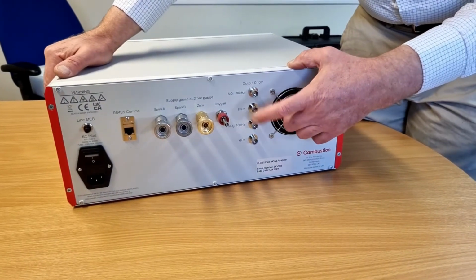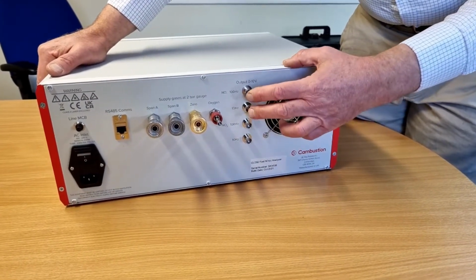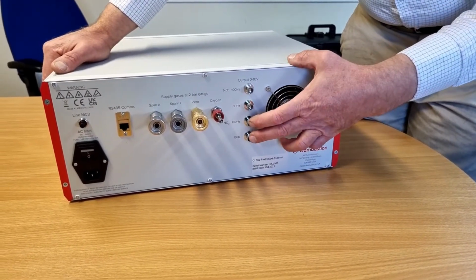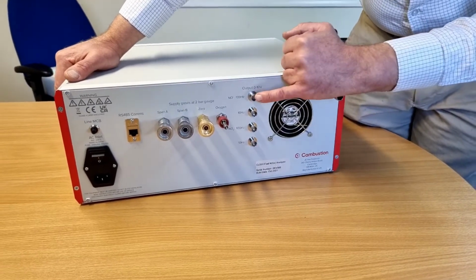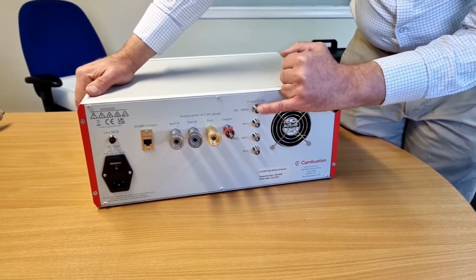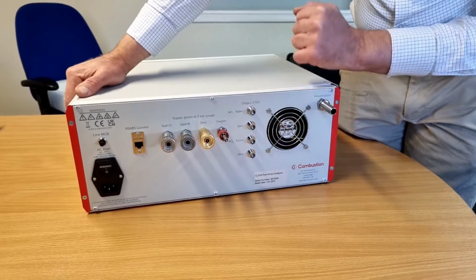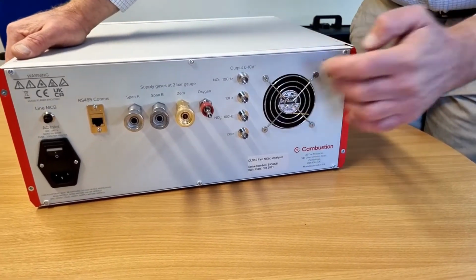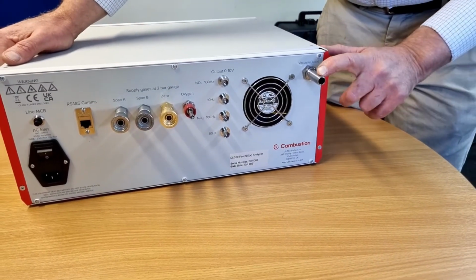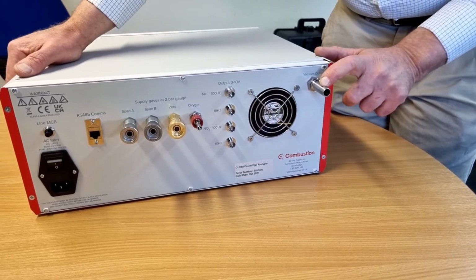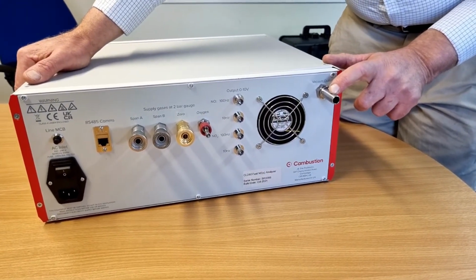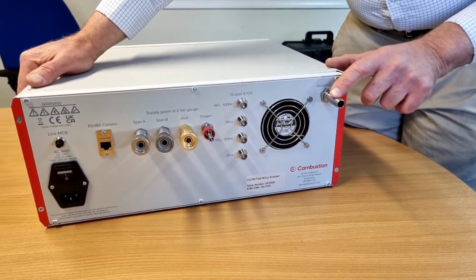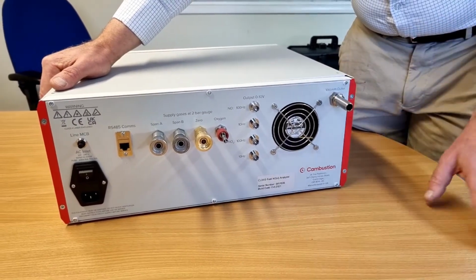These are 4 analog outputs, 2 each for NO and NO2. And there is a fast and a slow, 100 Hz and 10 Hz, outlet option. There's a cooling fan, and this is the exhaust from the analyzer. So this will exhaust at a flow rate of about 20 litres per minute, and this should be vented to an extraction system.